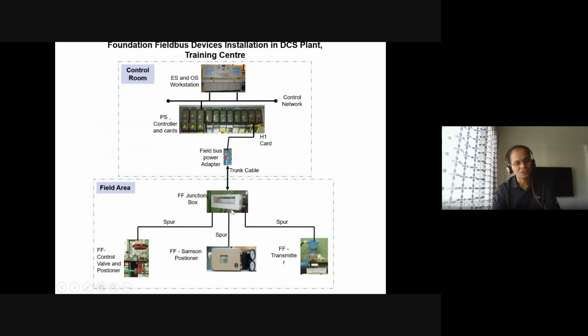This junction box is not a normal junction box. A normal junction box, which I have shown many times, is just an open termination block where you wire connections. This block has electronics inside, like a multiplexer and demultiplexer - just simplifying it. So this is the electronic device, and the signal from here goes in a single cable, the same type of cable, but here it is named the trunk cable.